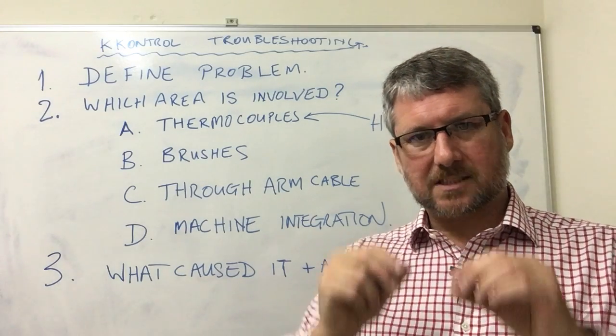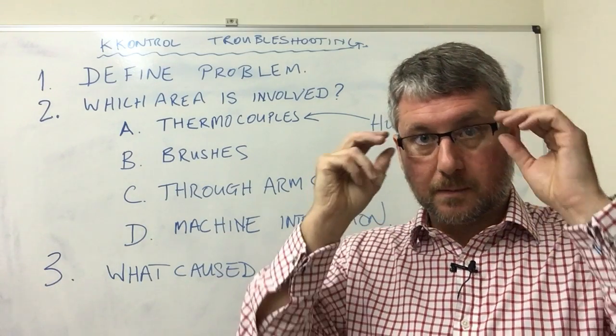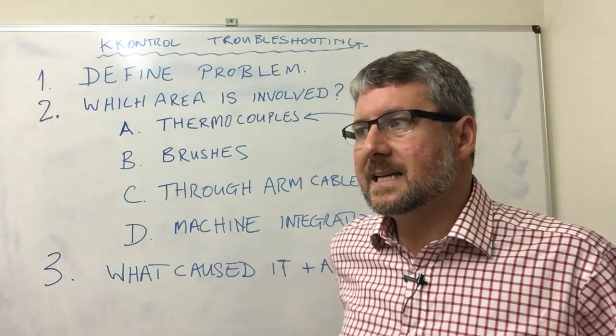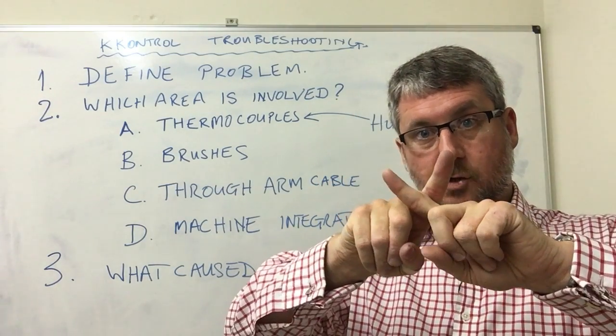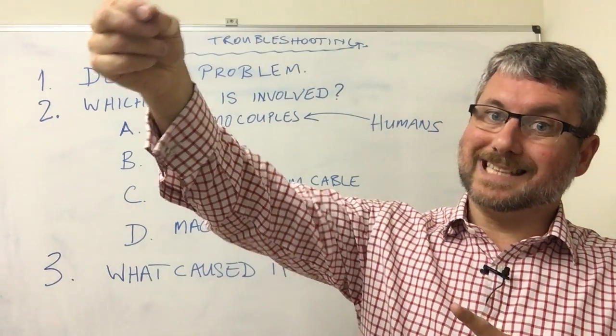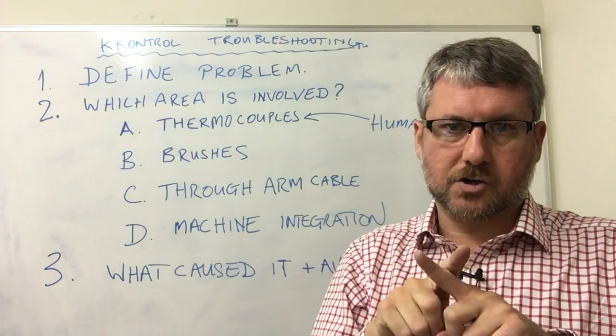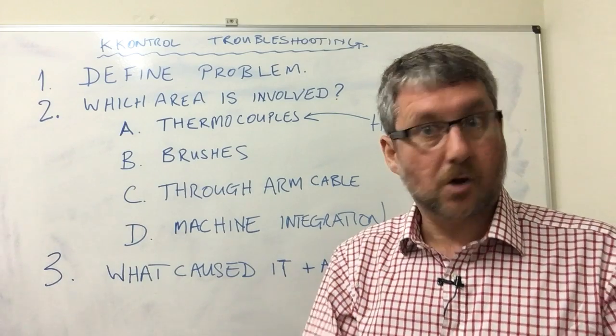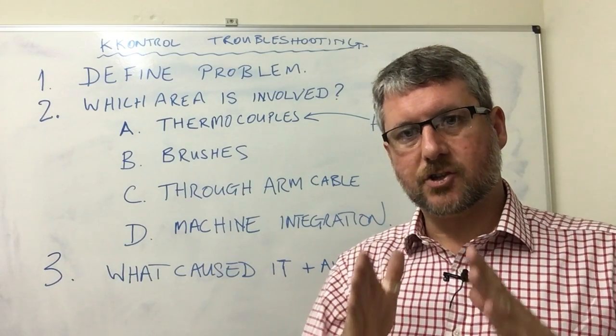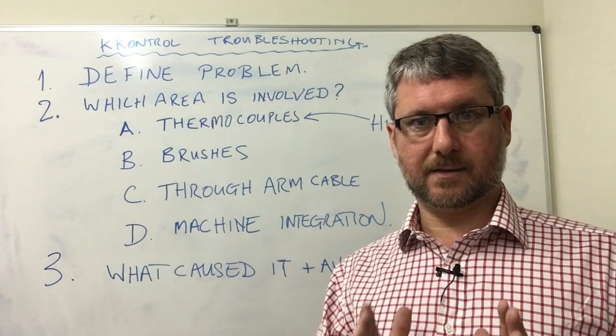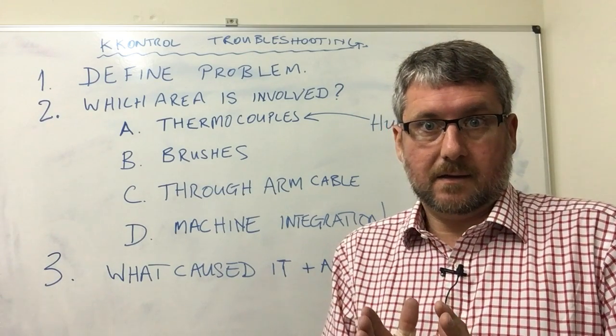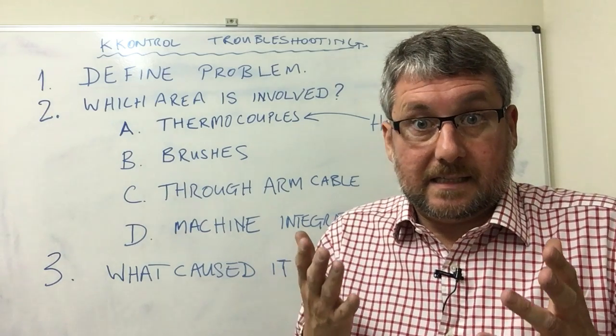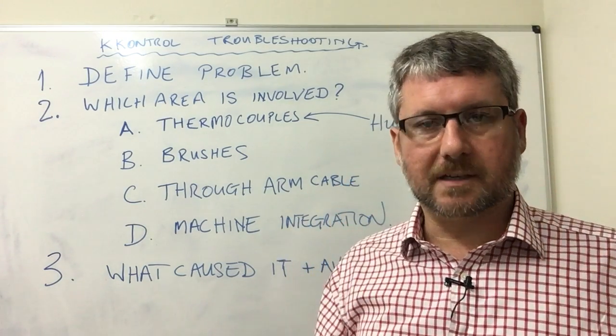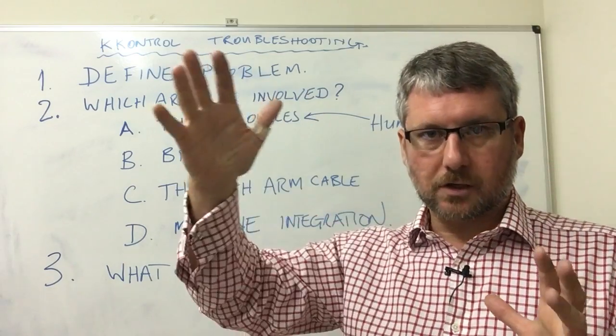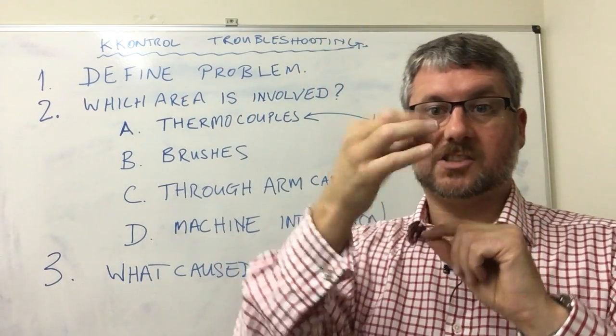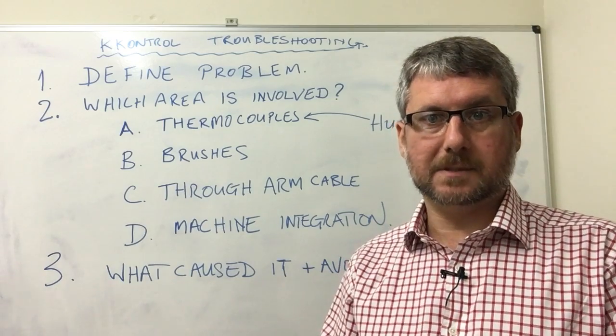The other biggest, most difficult problem to solve or to identify is if there's a short circuit between the two wires before it gets to the tip where it measures the temperature. If there's a short circuit in the plug or in the cable or in the slip rings, then what happens is you still get a temperature reading coming through. It looks as if it's fine. How do we know it's not the correct temperature? Through experience of knowing what the curves should look like and to know if they go outside the boundaries that we're expecting them to be in.